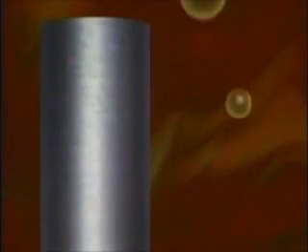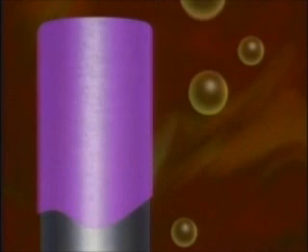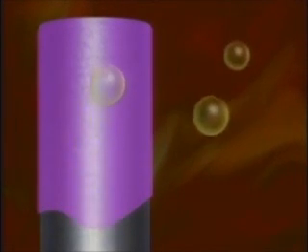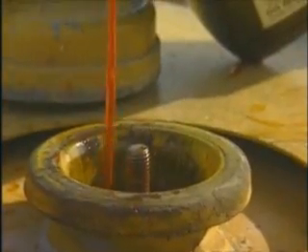Carboxylates outlast traditional corrosion inhibitors because they do not have to react with metal to form a barrier layer. They remain active even after cavitation chips away the layer and reattach to the surface to continue providing protection. The formulation does away with silicates and phosphates entirely.